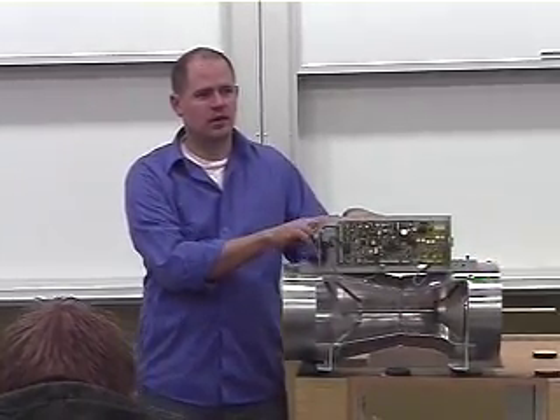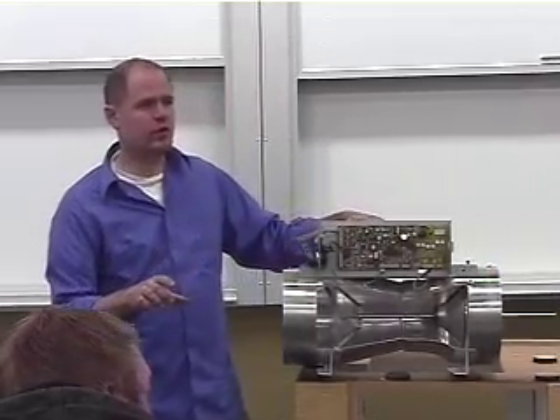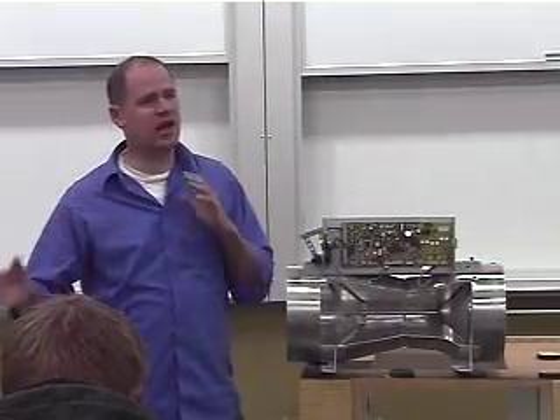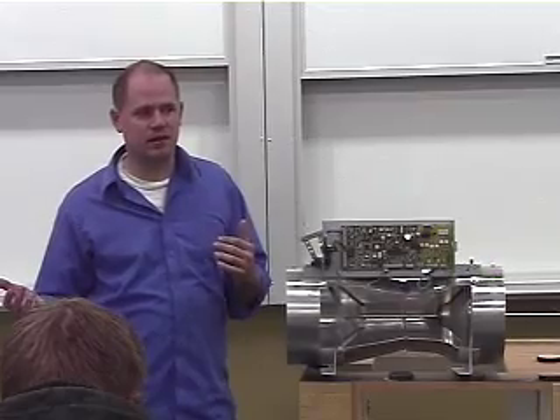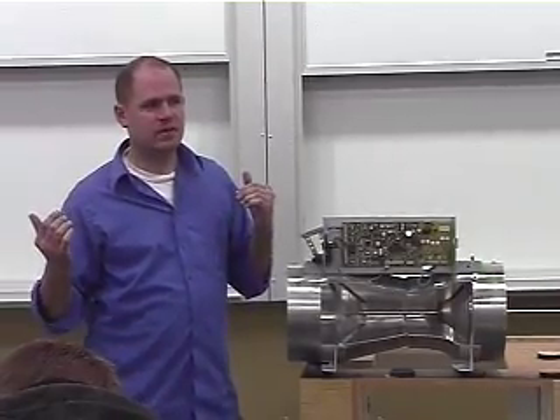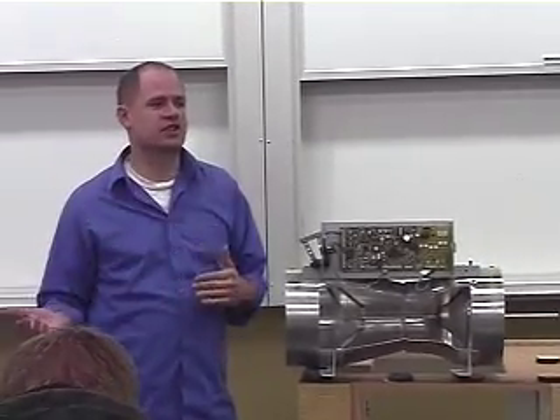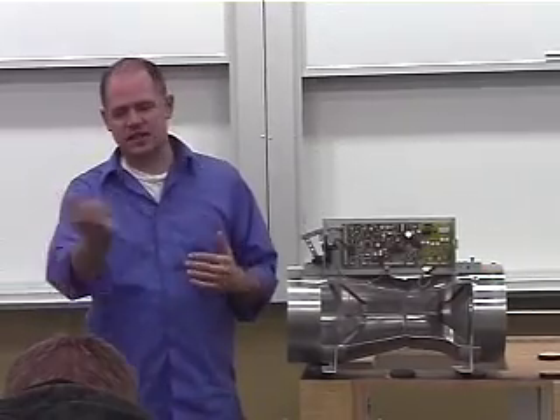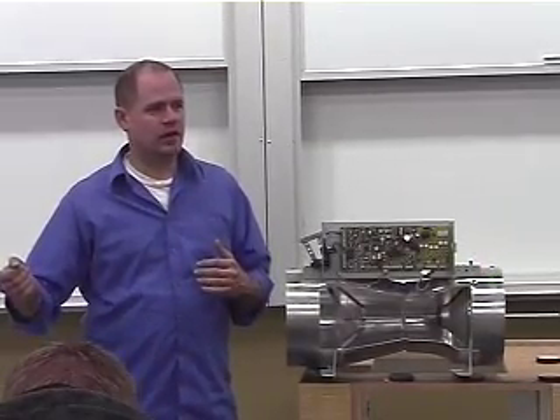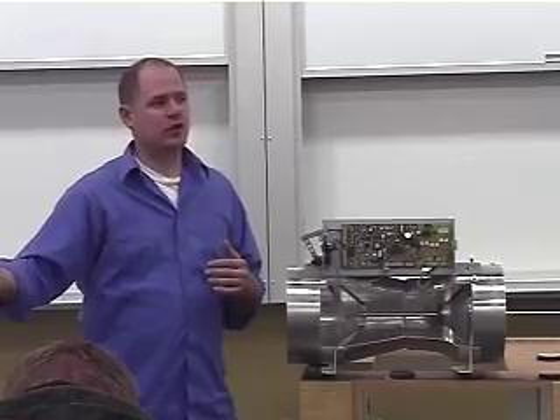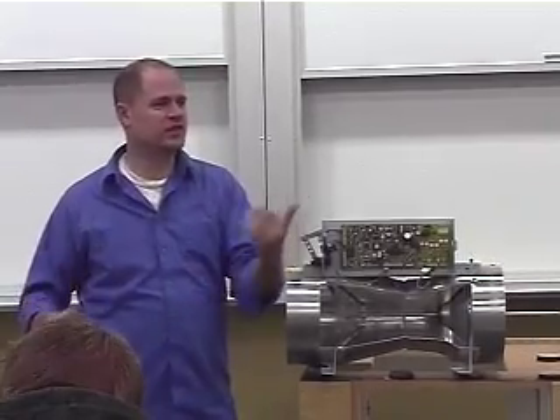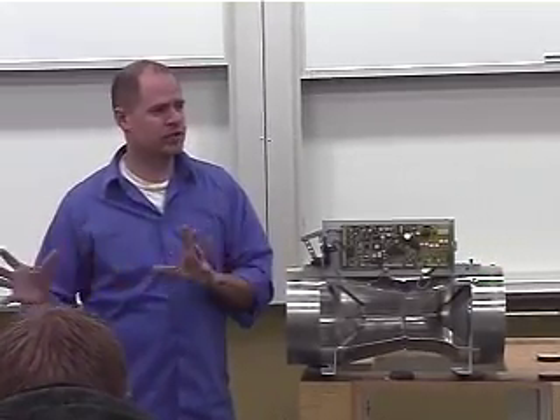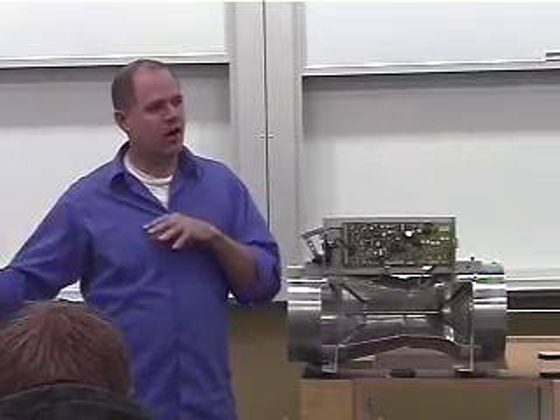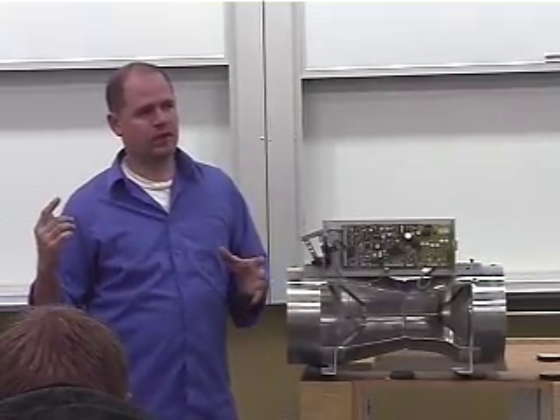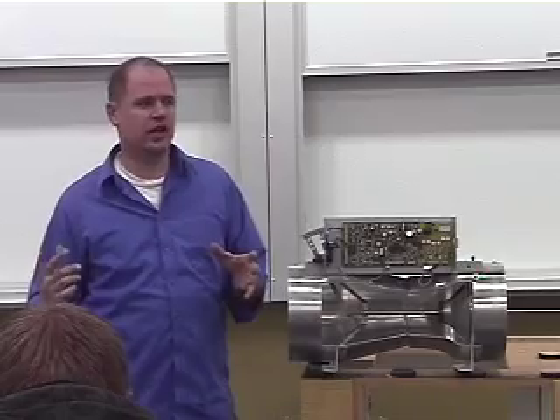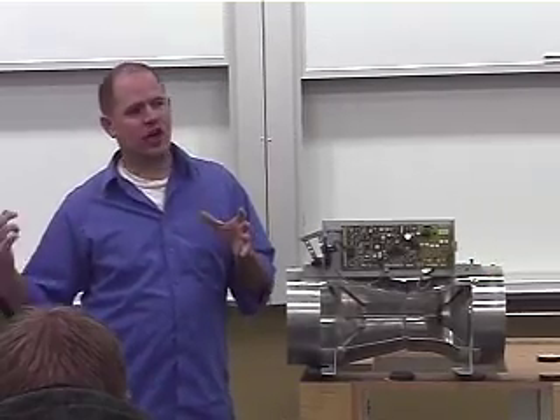And that's all the codes. Yes, all of your fume hoods, and any room that controls a fume hood, its supply and exhaust is also going to be on a high speed because it needs to be able to respond to what the fume hood changes are. Because the fume hood responds to the sash position. Then all of a sudden, okay, you've got more exhaust in the room, you need your supply to go down or your general exhaust to go down or up or whatever, whichever way you need to go. You need all of those to respond quickly. So in a lab with fume hoods, you're going to have high-speed control on every one of the valves.